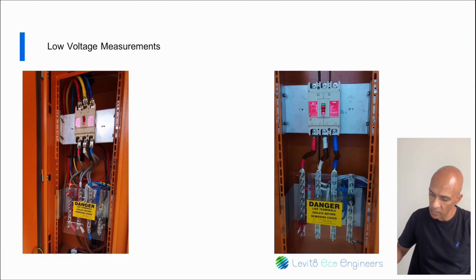So let's have a look at this picture. What we are saying here is we either measure at the top of the breaker or measure at the bottom of the breaker, but not here on the bus bar because you already have outgoing feeders from this bus bar. So you will not get an accurate reading. Let's have a look at this picture. Same scenario, and you do not want to measure down here. This is incorrect. Okay, those two are correct.